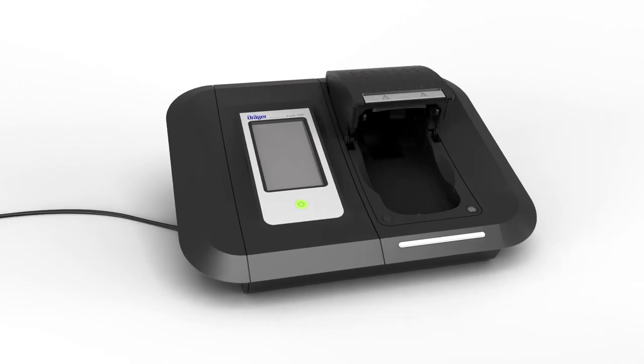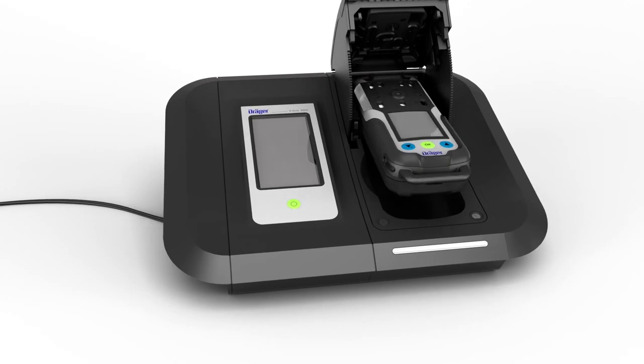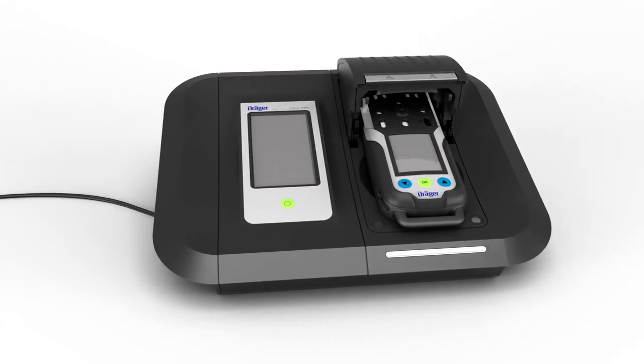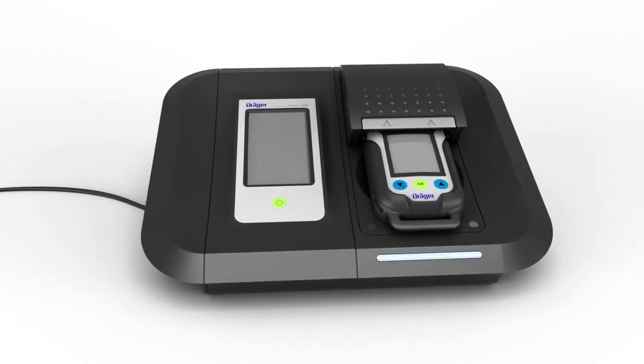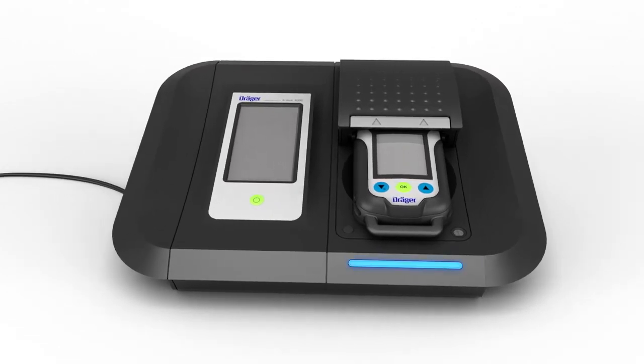You can also carry out a bump test using Draeger X-Dock, the automatic test and calibration station. Insert a device into the module. The Draeger X-Dock will detect the device and automatically record it in the integrated database. As long as the test is running, the module LED will flash blue.